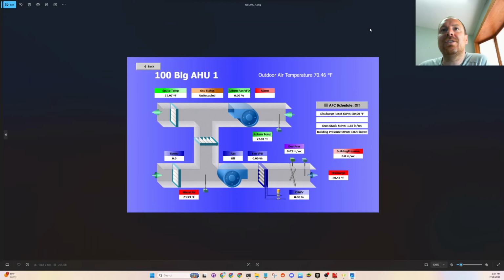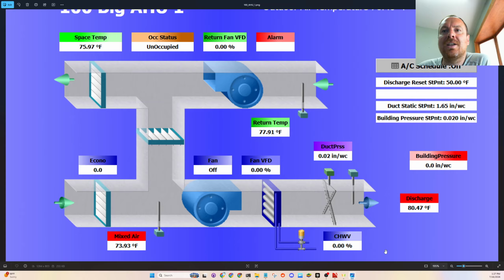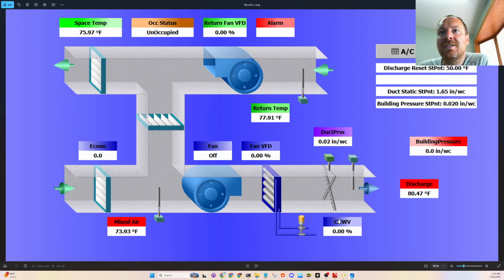The most ideal thing that you would want, which I've set some plants up like before, is that this cooling valve needs to be open some percentage, like 15%. Both air handling units need to have cooling valves open, maybe even 25%. So at that point in time, the air handling unit would be in economizer plus cooling mode, and we'd be completely maxing out economizer free cooling. This valve would be open, some interlock of like 20% or something, and then we bring on the chiller.